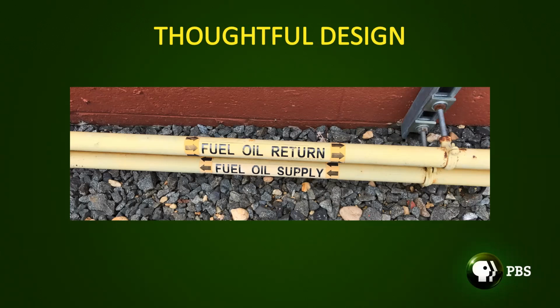That does two things: it helps make sure the fuel doesn't turn to jello in the day tanks, and it also means the fuel gets stirred, which keeps it from separating and stratifying. So for a little bit of electrical power and some maintenance, we continue to help maintain the integrity of our fuel supply. That's, once again, thoughtful design. The manufacturers don't suggest it, but it's the kind of thing that can make a big difference in whether or not the generators are reliable.